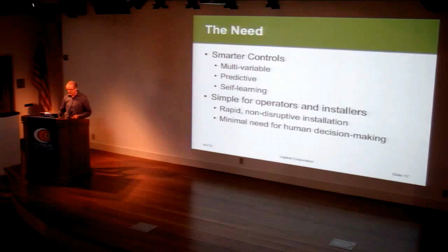The software itself is predictive. What we have, well, it's a transfer function for those of you who know what that is, but we refer to it as an influence model. And what it tells you in this case is the influence of this air conditioner on all the sensors. In this case, we had about almost 50 temperature sensors on this 10,000 square foot floor. The blue means that this one will cool these spots on the floor, these 3 server clusters.